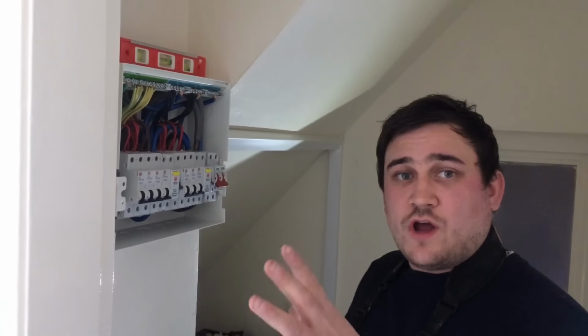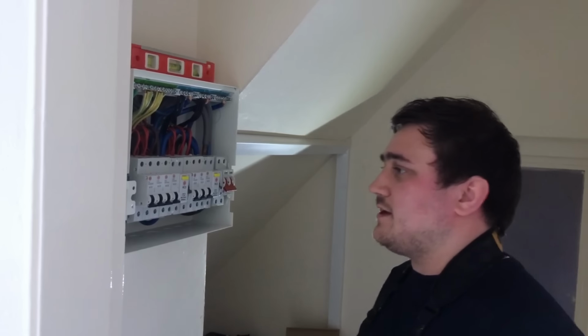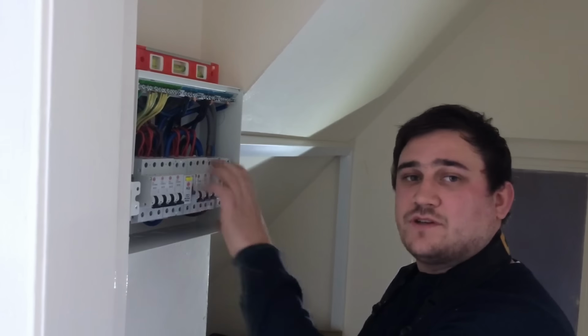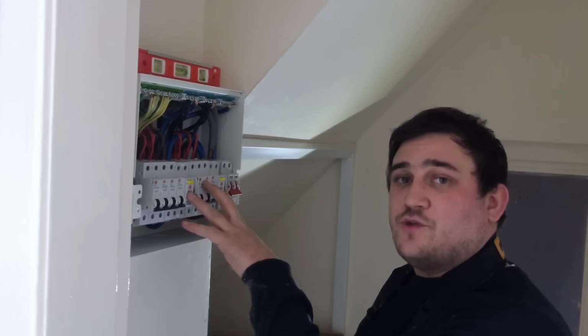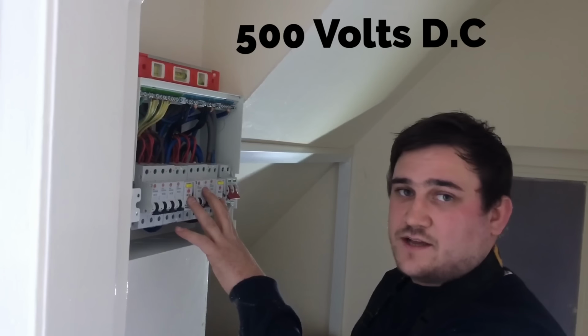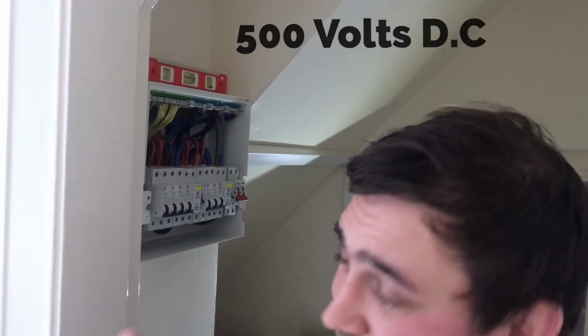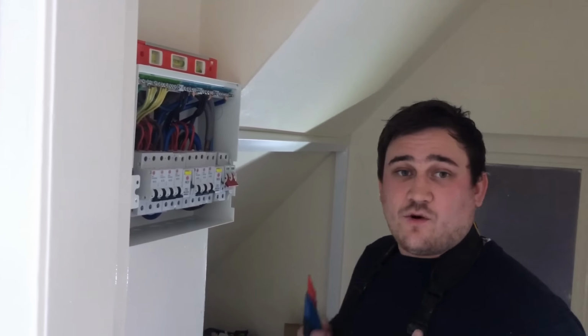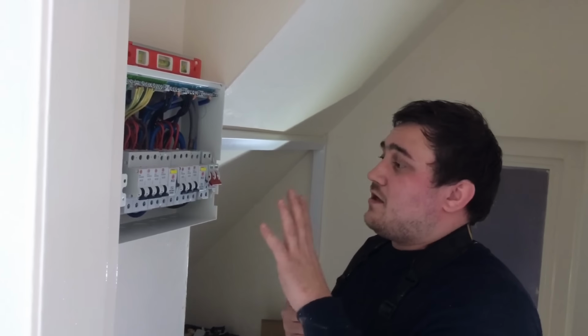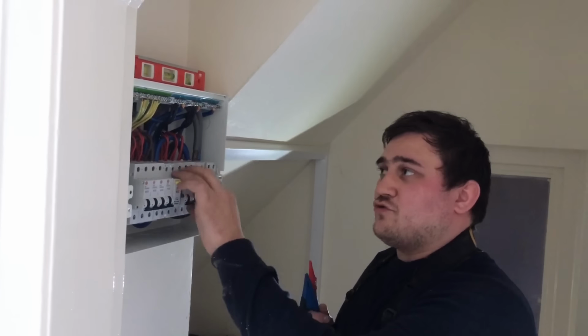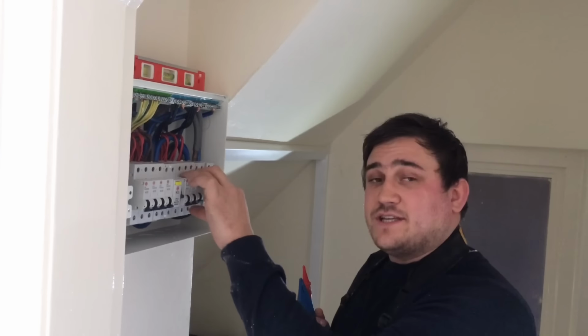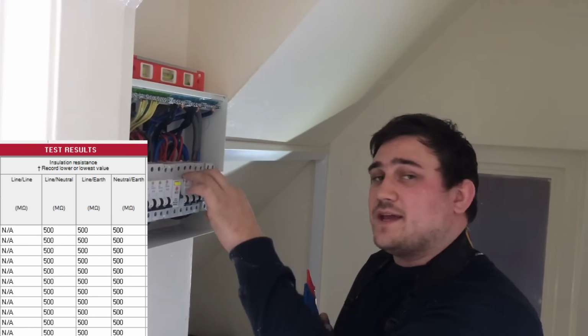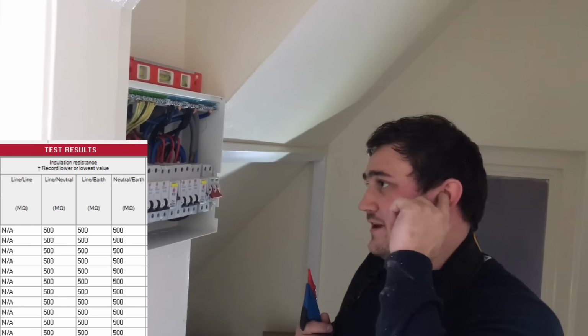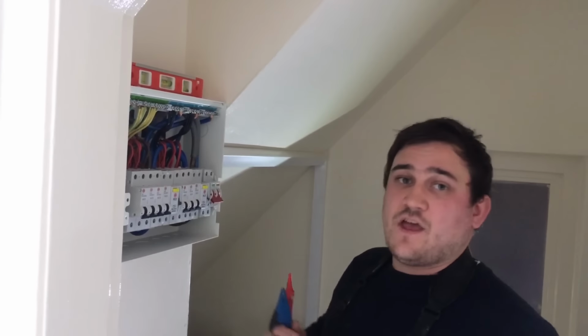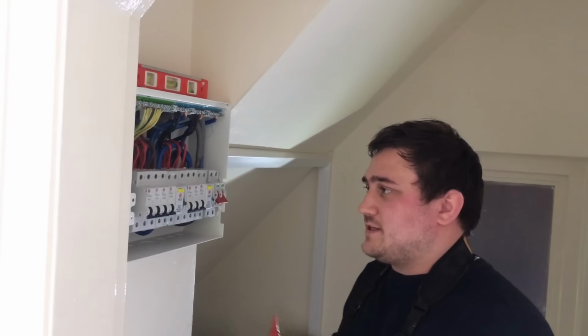I've made sure all loads are out of the circuit, i.e. lamps, neons, anything plugged into the ring circuits. All RCDs are turned off because they have electronic components in, so that could be damaged by the DC voltage from the tester. The smoke alarms are battery, so we don't have to worry about them because they're not wired into the circuits. I'm going to go between line and neutral first, as the NIC domestic installer paperwork allows me to do so. The BS7671 actually only allows you to do between live conductors and earth, where we would have to link them together. We don't have to in this case.